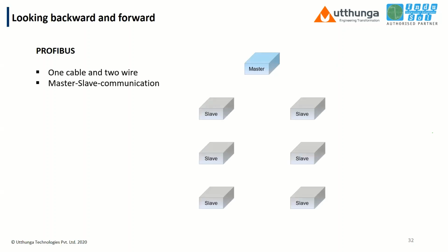Right now I'm taking you through a small exercise to rewind what we just studied. So what is Profibus? Profibus is Process Field Bus, with one cable and 2 wires. It is RS485 communication, simple. And it is master-slave communication technology, with only one token or one packet at a time. Unicast. Okay. You can see master and slaves. Then what do we need to start the communication? Address. We studied that 0 to 124 is the maximum we can go up to, right? So 0 to 125.